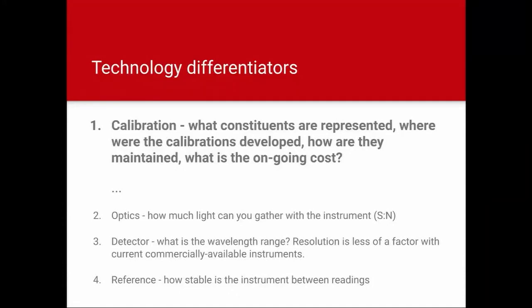Then I put three dots because way further down the list are things you should be concerned about. What kind of optics does the instrument have? How good is the instrument at gathering light? We're talking about signal to noise ratio. We want to make sure that we're getting a lot of the reflected light back into the sensor and imaging that light so that we can get a good idea of the chemical makeup of that sample. Once you have good light in the sensor, you want a detector that has a good wavelength range. Applied research in this area has found that resolution is less of a factor with the current commercially available instruments. Nobody's really cutting too many corners on that, and they all seem to perform quite well. We've even done work where we've artificially reduced the resolution of the spectrum and predicted samples, and that works quite well. And then, how stable is the instrument between readings?